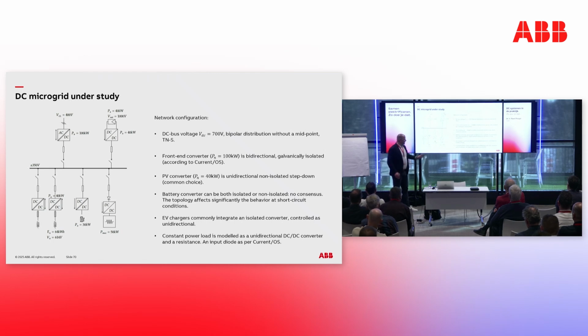One reason is that if you have, for example, a battery and an isolated converter, you simply stop switching the converter, and then you don't have the short circuit contribution from the battery. If you have a non-isolated converter for the battery, for example a buck-boost solution, what's inevitably going to happen, even if you stop switching, is that the antiparallel diodes, depending on the topology, can still conduct into the short circuit current. So all these things you need to consider.